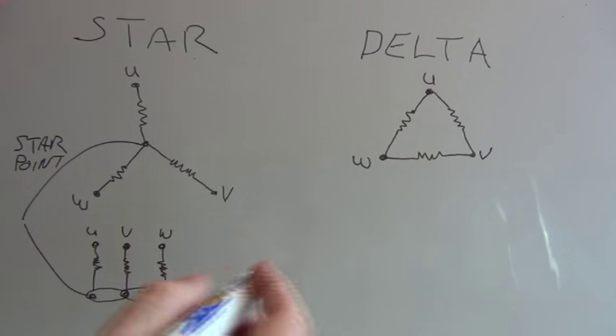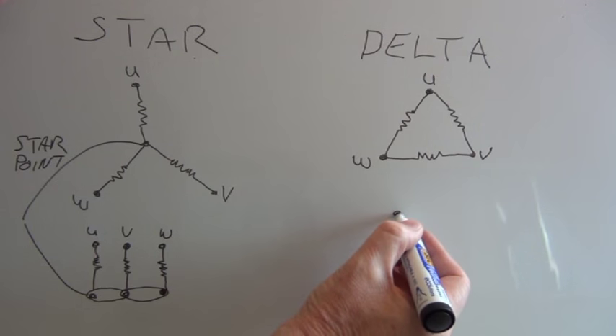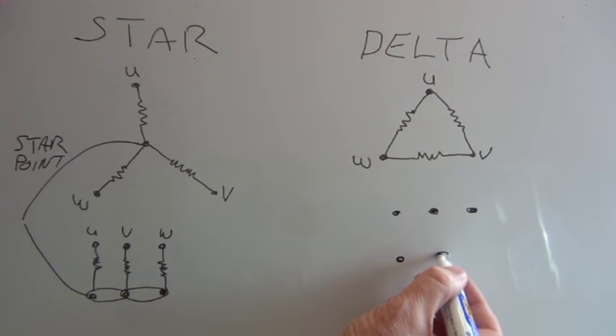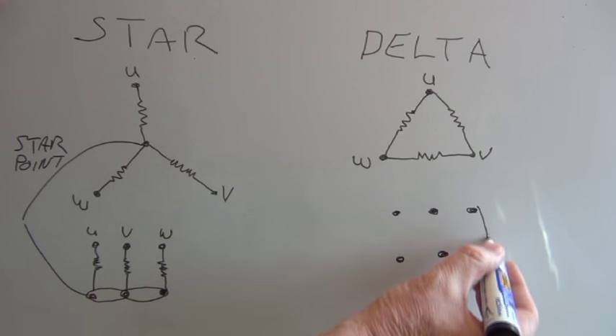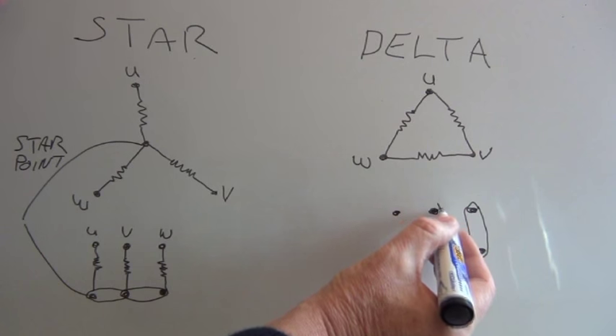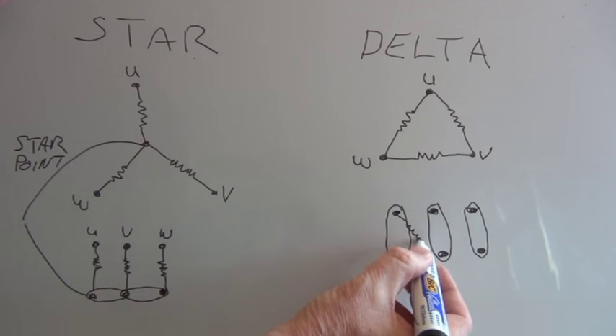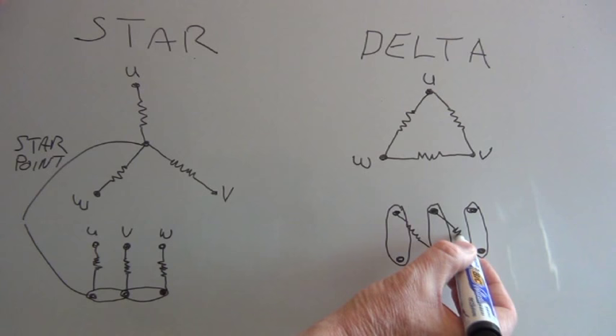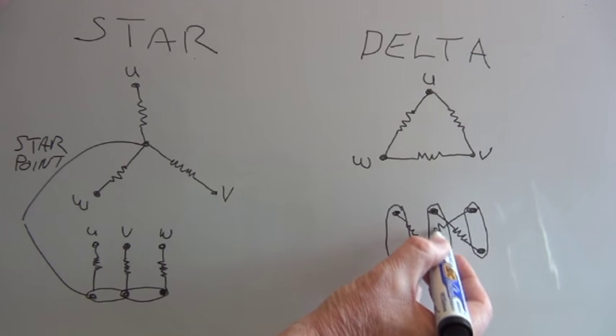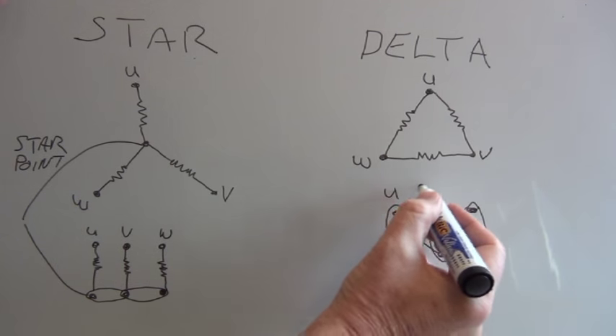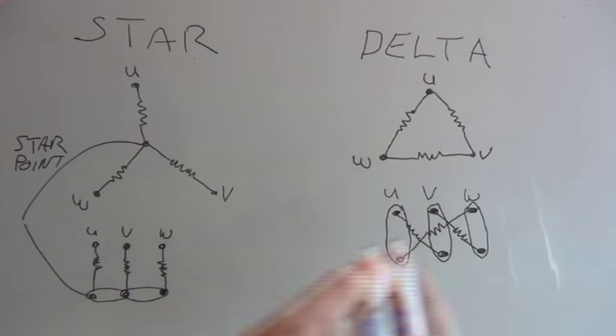If we look in a terminal block of the motor for the delta connection, we have this configuration where we have the six terminals, but this time the links go across the terminals like so, and the internal windings are connected in this configuration inside the motor. So we have U, V, and W, and that gives us the delta connection.